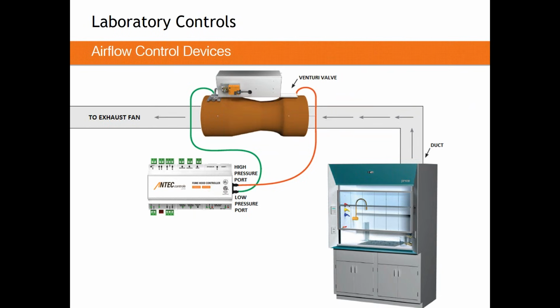What this is going to let you do is fan static reset. So once your system is up and running and it's been built exactly as you designed, you're able to intelligently reset these systems down to save a little bit of horsepower and a little bit of energy. All of that data is available over the building network, and for fume hoods, available right at the fume hood as well.